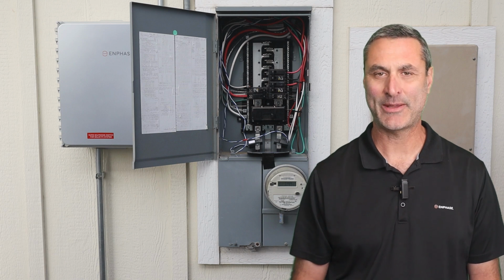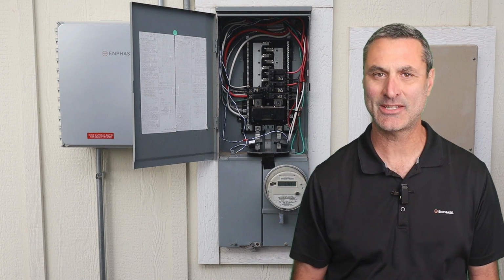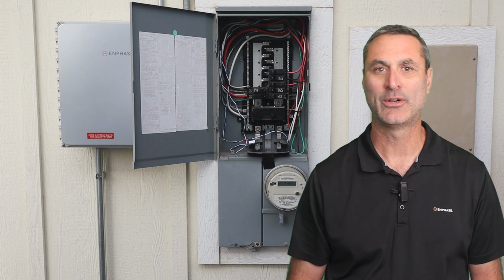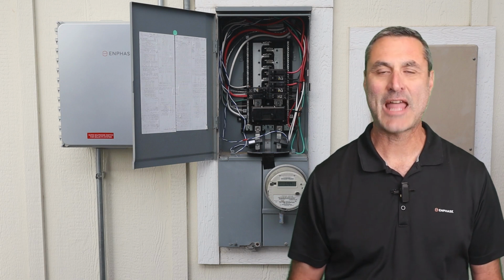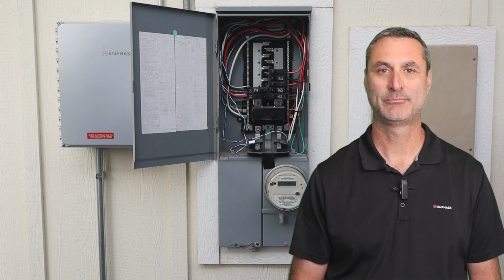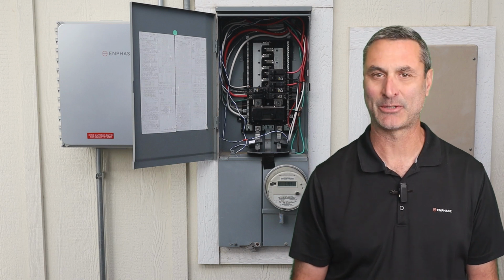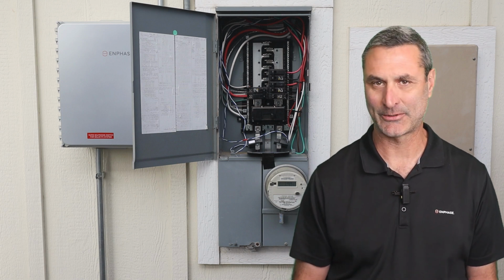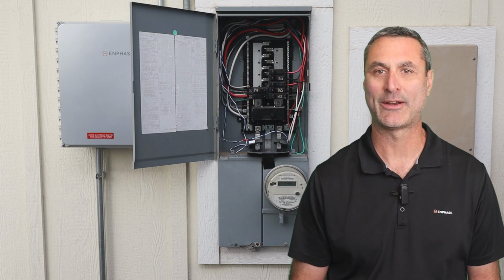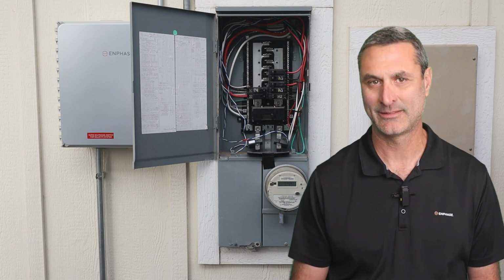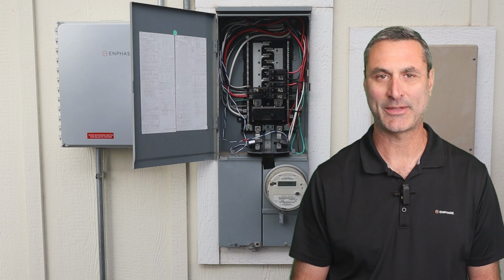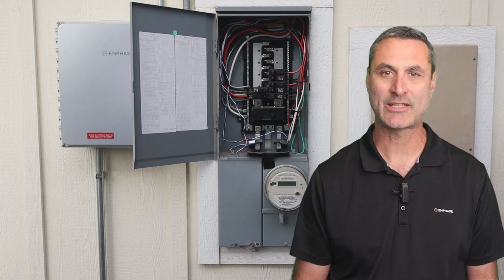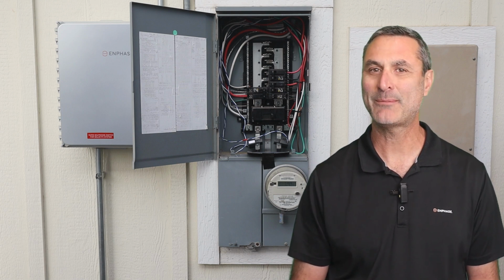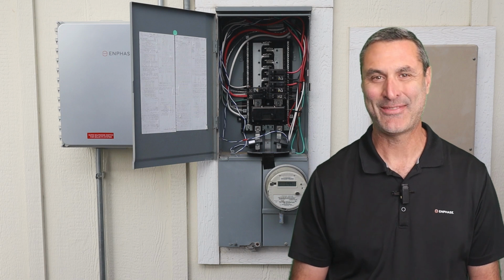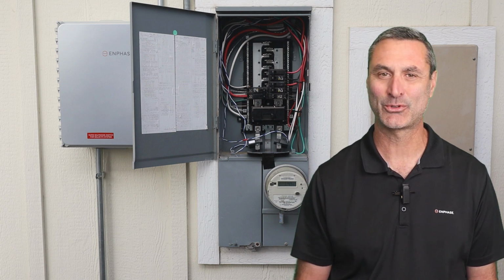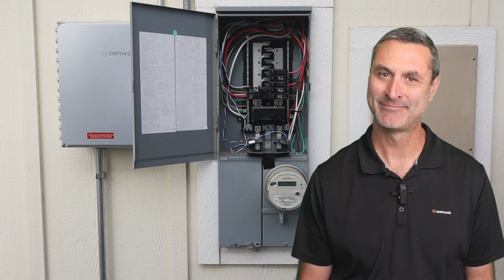It analyzes all the information from the CTs, and it makes real-time decisions about where all that electricity should go. Now, there are several different applications for Enphase Power Control, but avoiding main panel upgrades is one of the most popular. They cost around $4,000 or even more if trenching for new utility wires or relocating a gas meter is required. They're also a big hassle for both the installer and the homeowner, and can add weeks to the installation timeline. Avoiding main panel upgrades makes everybody happy, and the homeowner can put the money they saved toward more solar panels or a larger battery.